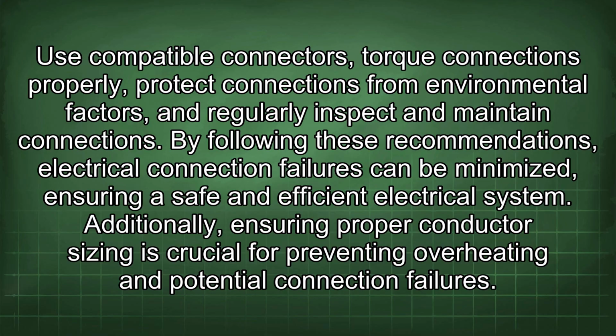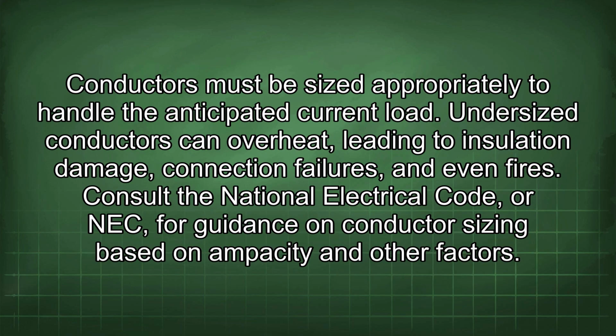Additionally, ensuring proper conductor sizing is crucial for preventing overheating and potential connection failures. Conductors must be sized appropriately to handle the anticipated current load. Undersized conductors can overheat, leading to insulation damage, connection failures, and even fires. Consult the National Electrical Code, or NEC, for guidance on conductor sizing based on ampacity and other factors.